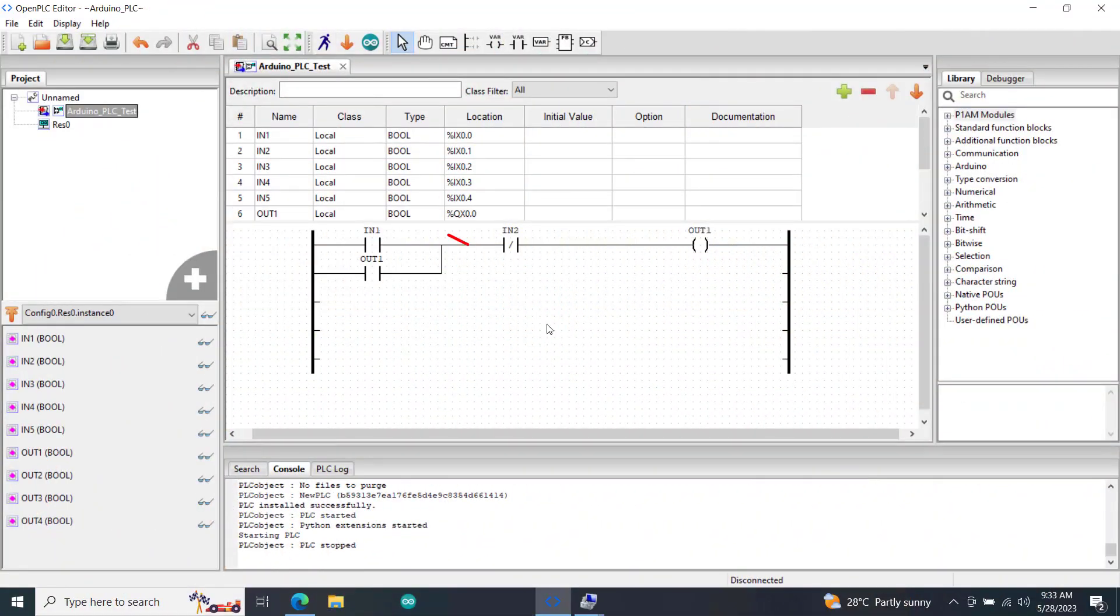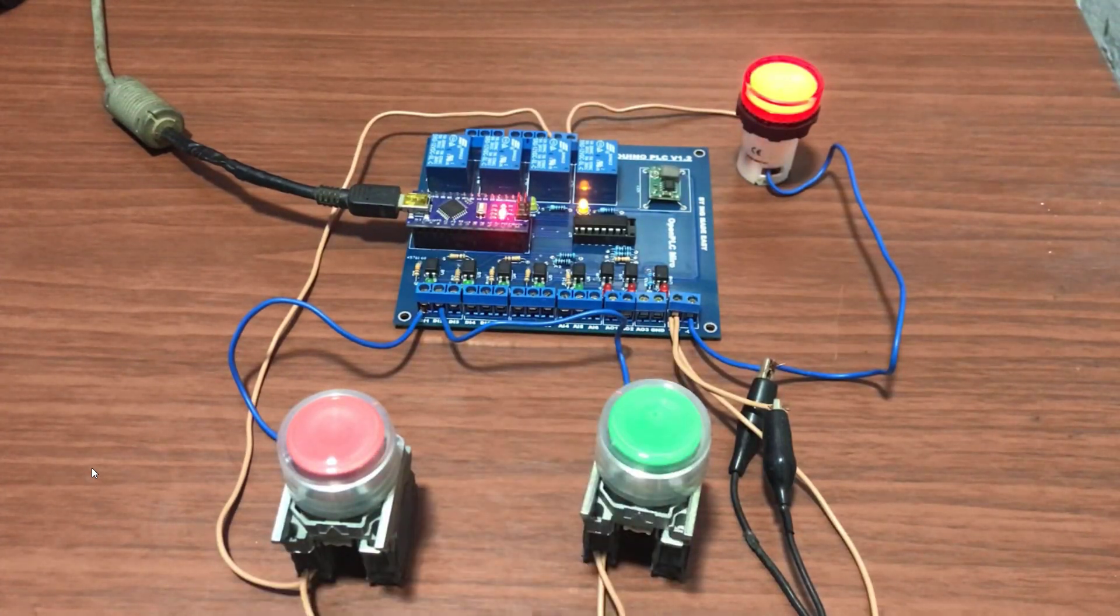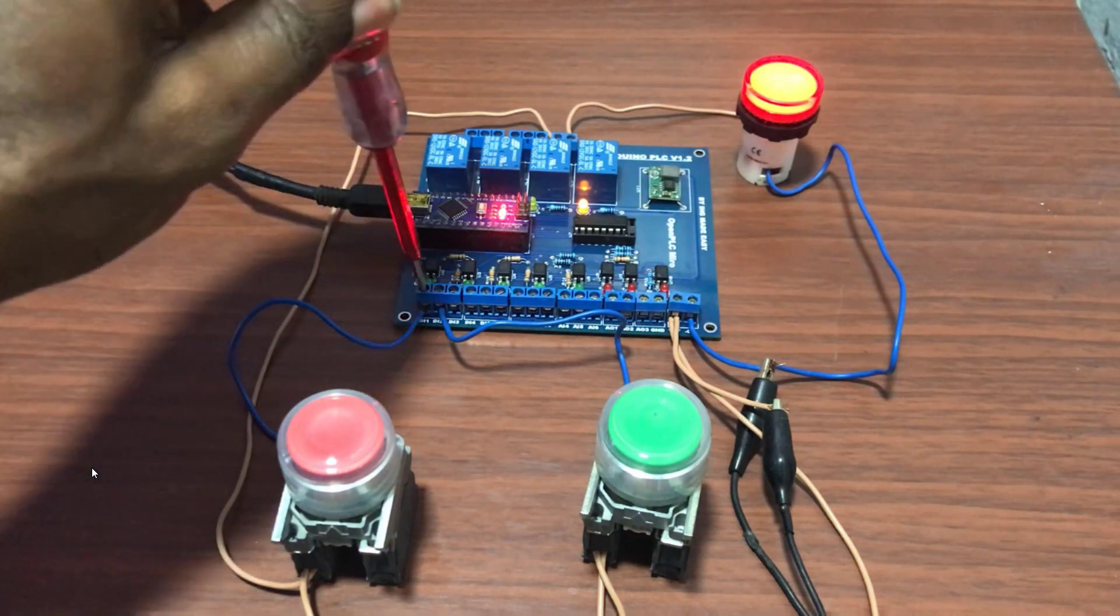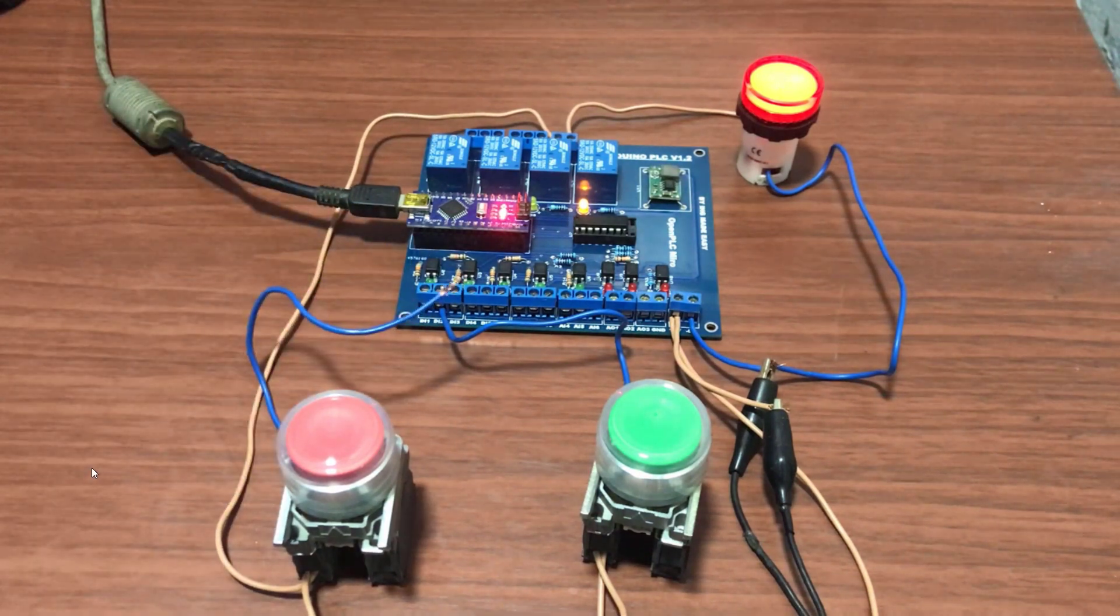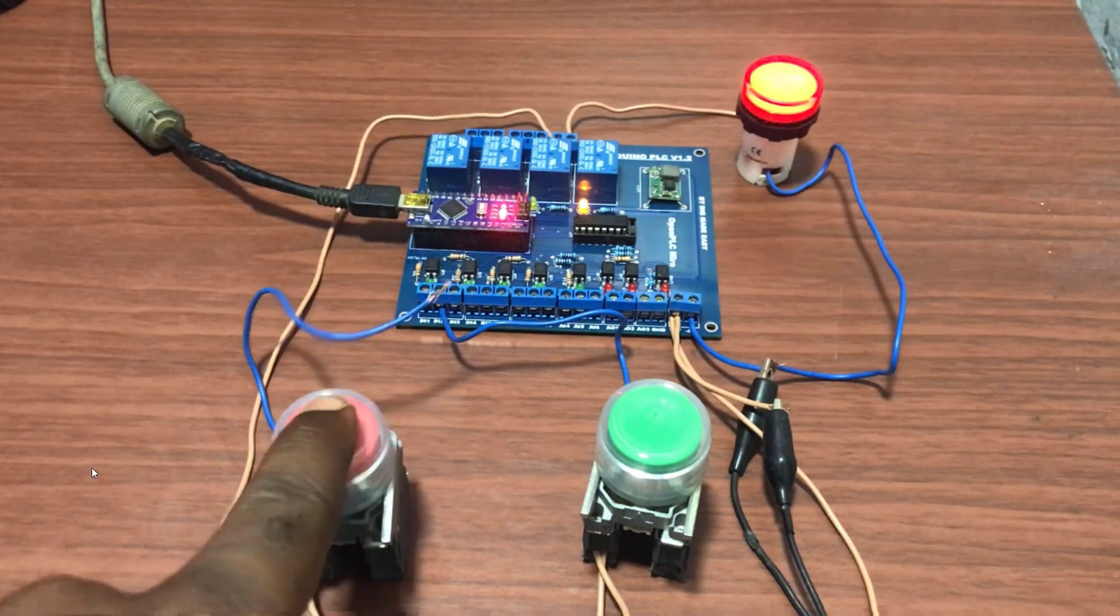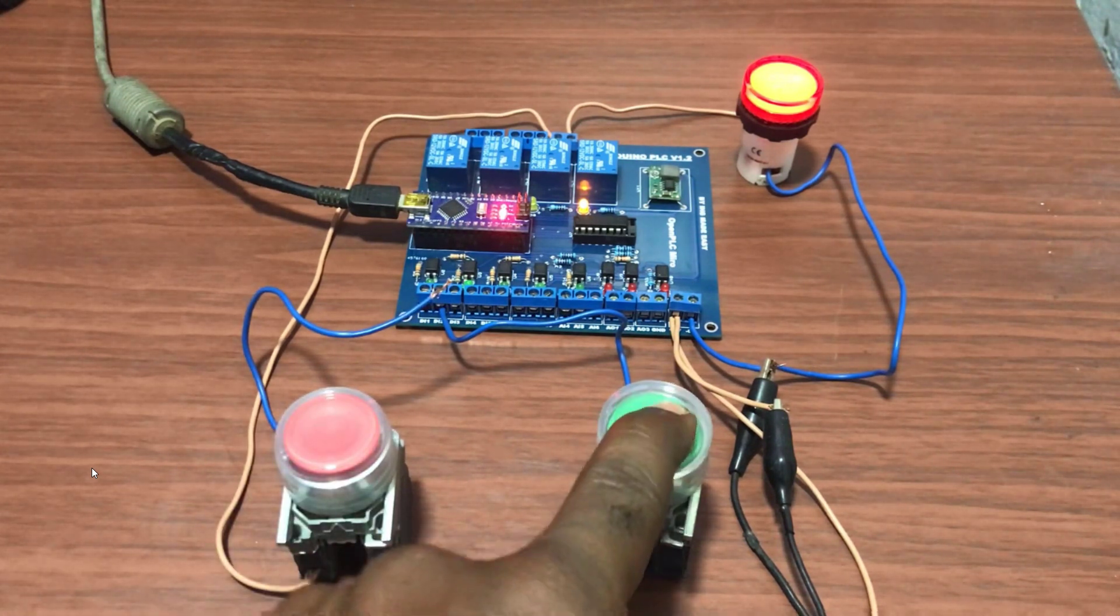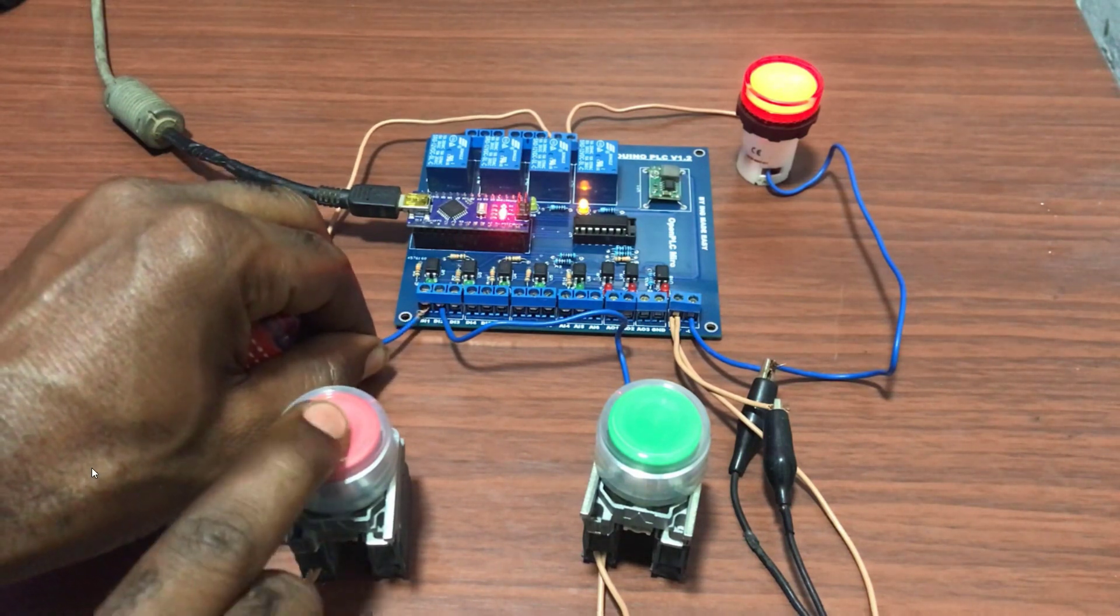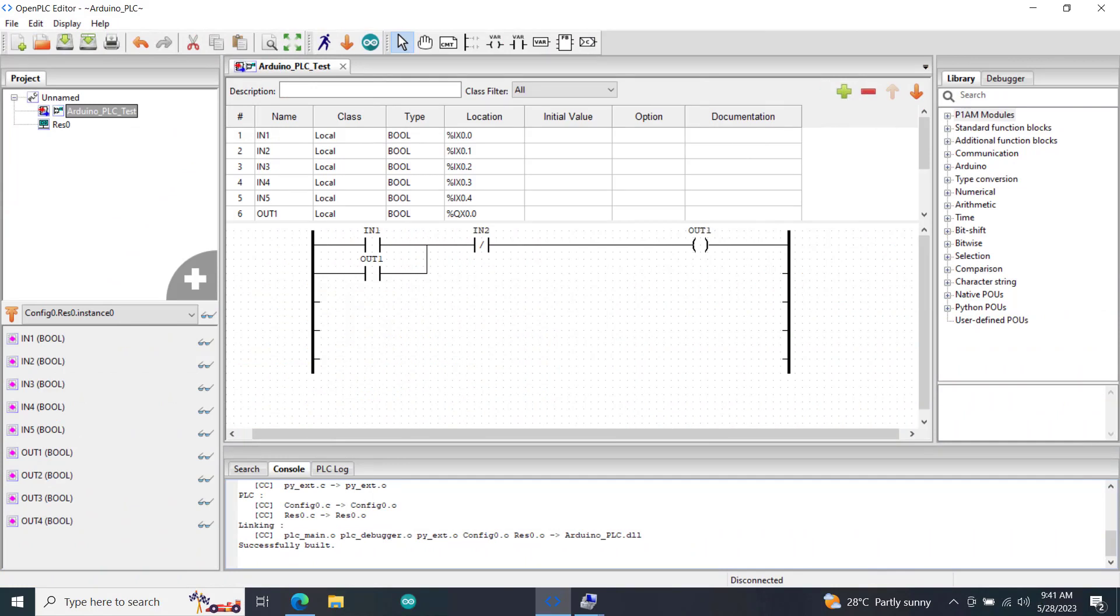Now let's see how this circuit works when there is a fault introduced in our stop push button. We can see our lamp coming on when I press the green button. We now introduce the fault in our stop push button. And then we can see that when this is introduced, now I cannot put the lamp off until I correct this error which is really dangerous for operators.